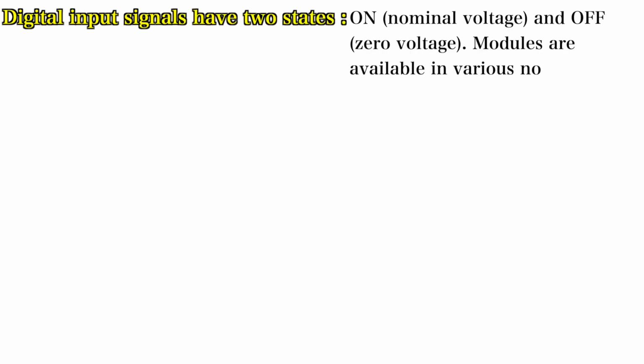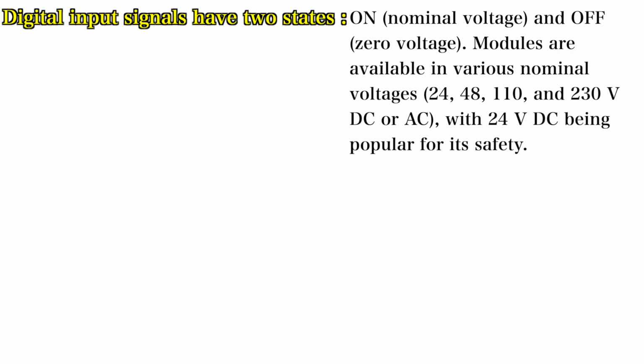Next, these signals are then multiplexed and transferred serially to the microprocessor through many smaller PLCs or through mainly smaller programmable logic units, which may use parallel transfer without multiplexing too. So these digital input modules provide visual indicators for each input state, meaning they can use an LED or neon lamps for indication. The digital input signals have mainly two states, on and off. The on state indicates the nominal voltage, while the off state indicates zero or null voltage. The modules are available in various nominal voltages like 24 volt, 48 volt, 110 volt or 230 volt DC or AC, but 24 volt DC is the most popularly used for its safety.